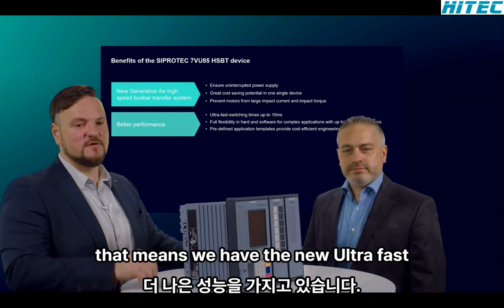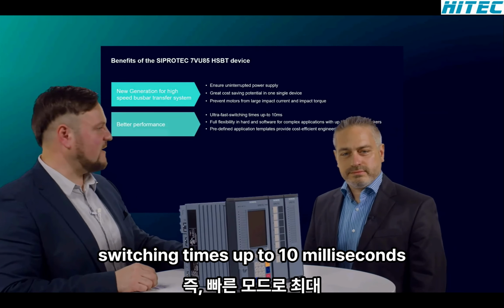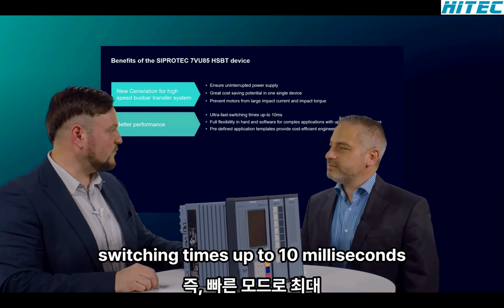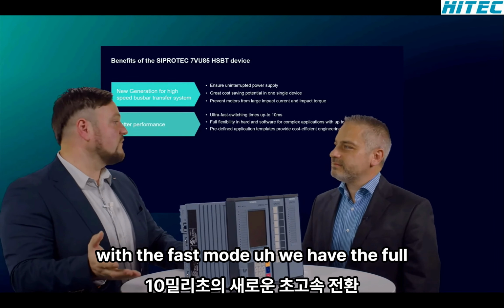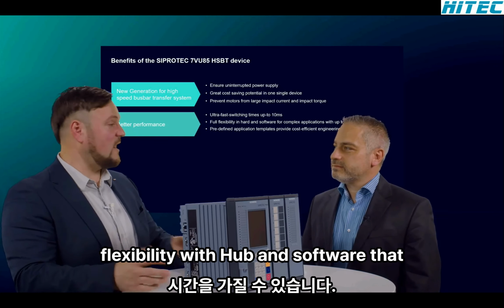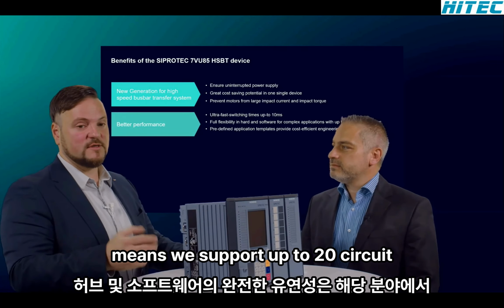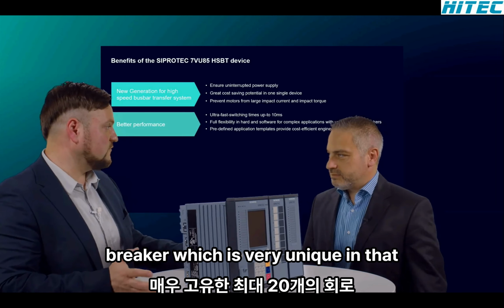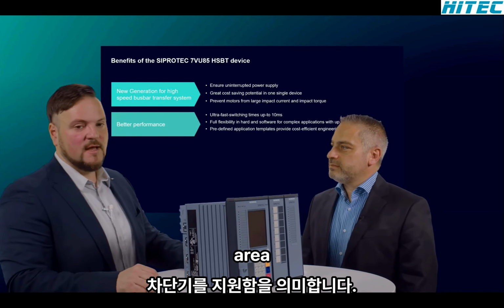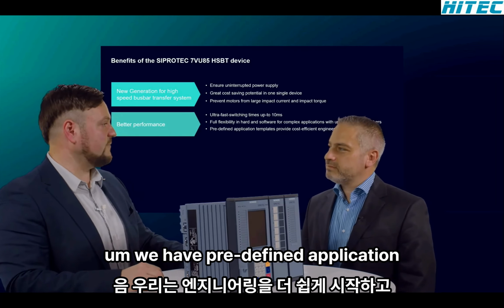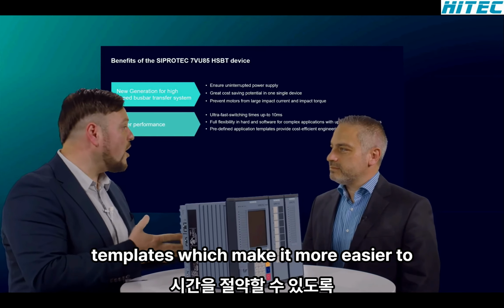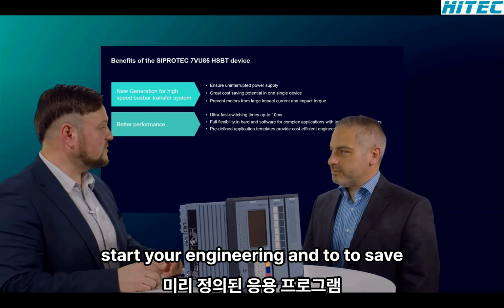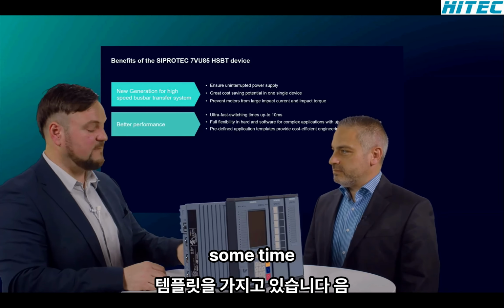That means we have the new ultra-fast switching times up to 10 milliseconds with the fast mode. We have the full flexibility with hardware and software. That means we support up to 20 circuit breakers, which is very unique in that area. We have predefined application templates, which just make it easier to start your engineering and to save some time.